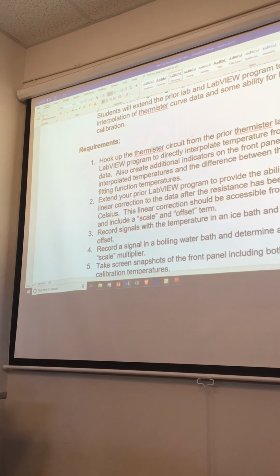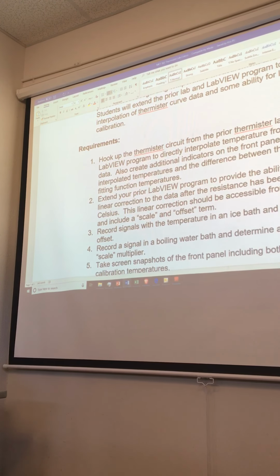Now, what we're basically going to do in some sort of linear calibration is we have a linear function. So we're going to say that our calibrated value is equal to some m times y uncalibrated, plus b. And m and b are our calibration factors. They're things that we're going to have to enter to perform the calibration.